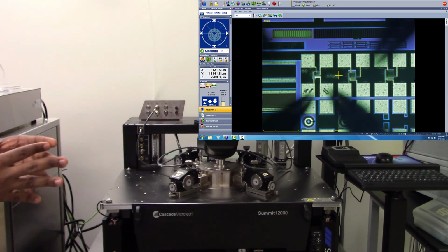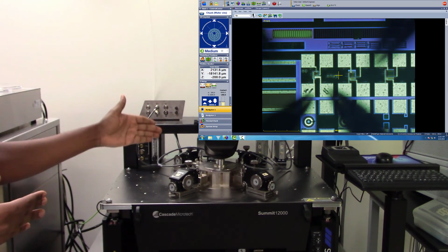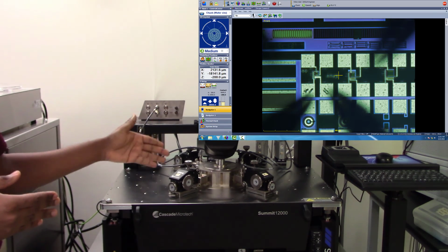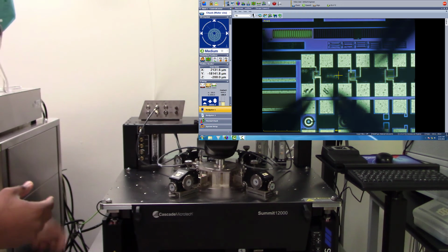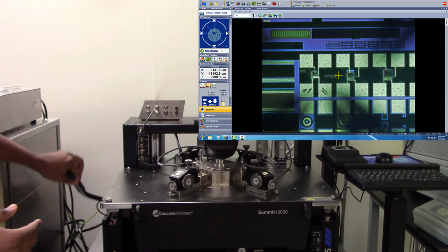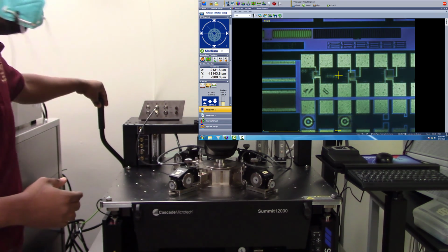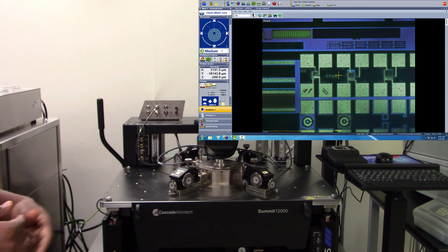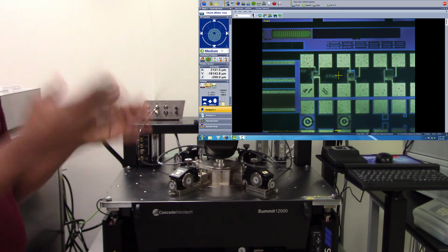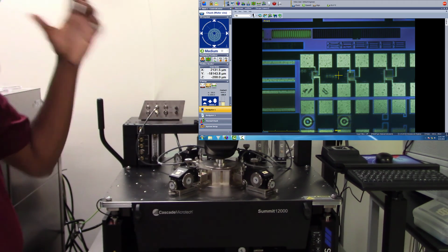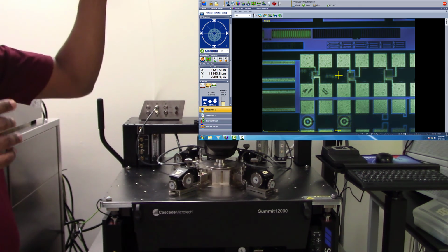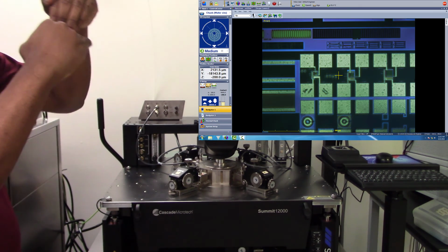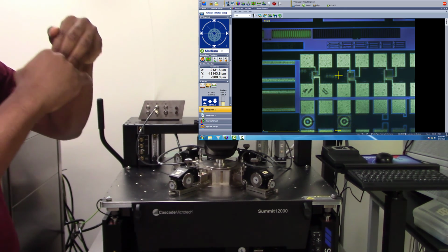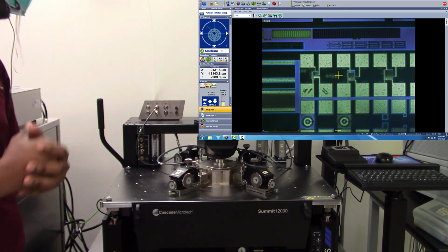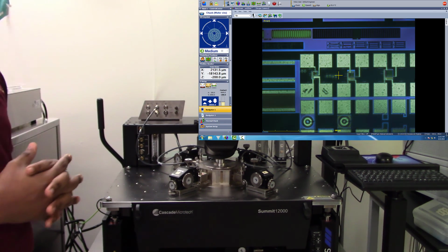Once that is done and all measurements have been taken, you've rotated back your Z position for your micropositioners counterclockwise for around 10 rotations. Then you need to slowly bring back your platen lever to make sure that your probe tip does not come so close to your sample. And that is how you primarily land your probe tip on any kind of device you have, verifying that you have a scratch on your device and making sure you are in contact mode so that your probe tip and your sample are in contact. That way you can pass either current or voltage into your sample to make sure that you have a good measurement. And that is all that we have to do today.